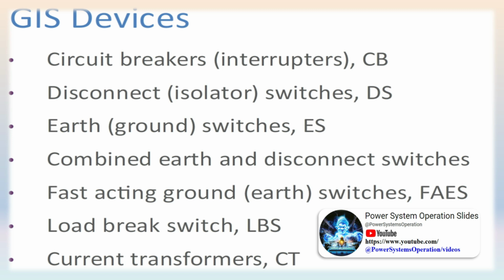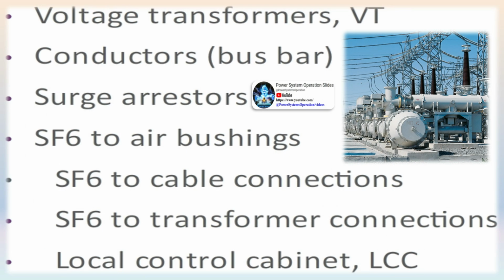The GIS system's foundation. GIS systems are usually installed on a monolithic concrete pad or directly on the floor of a housing facility. The system is attached by bolting or welding the GIS support frames to embedded steel plates or beams, or by the use of chemical drill anchors. Expansion joints. Expansion drill anchors are not recommended, as the dynamic loading from circuit breaker operations may loosen the expansion anchors over time.